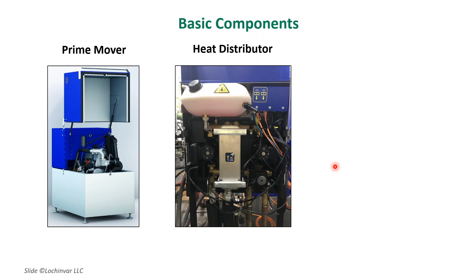On the control panel - this is the interesting part about micro-cogeneration - the electrical connection is not complex. This is a 480 volt three-phase system. If you have a 208 building, which we've installed in, simply adding a transformer to the project resolves the issue.